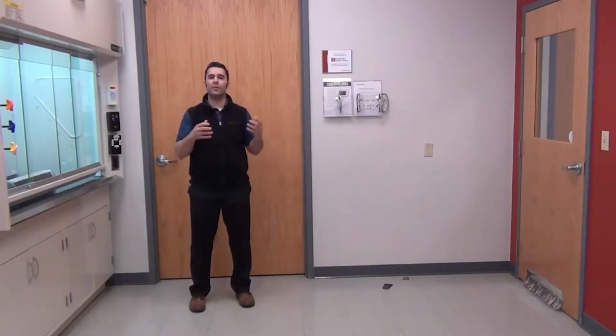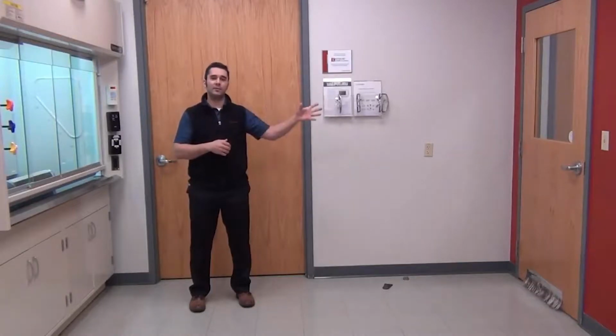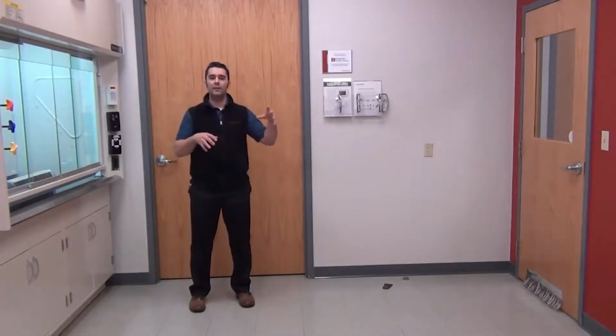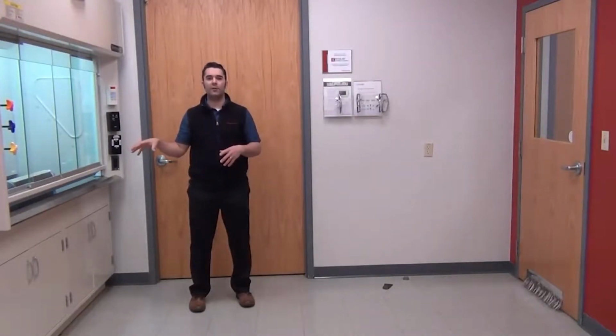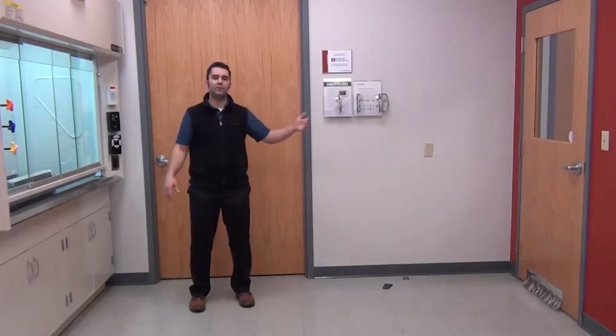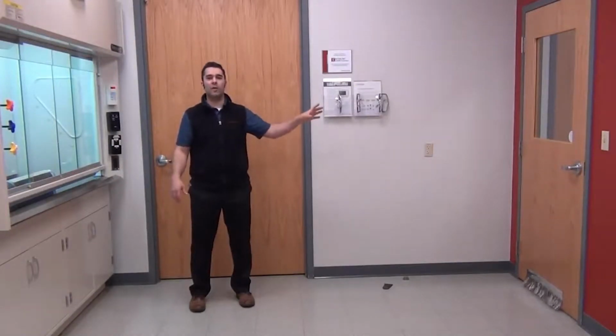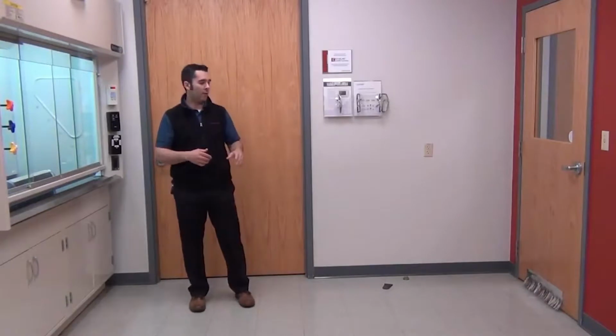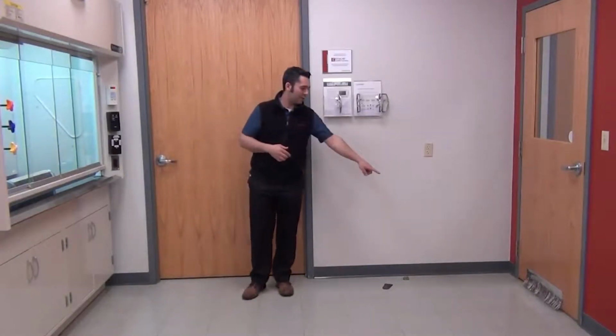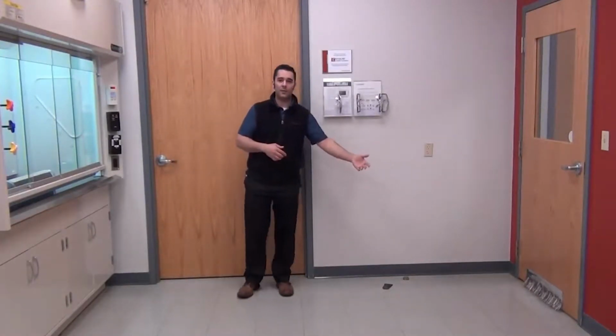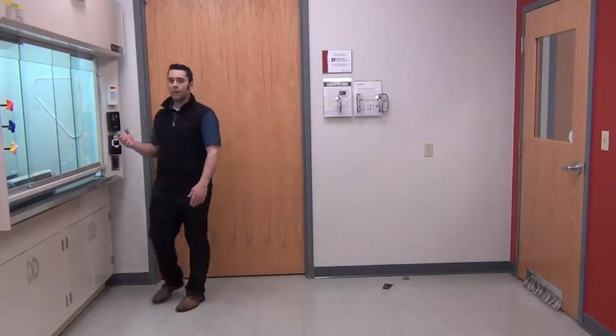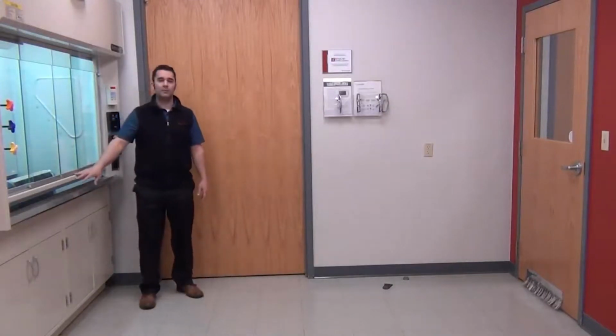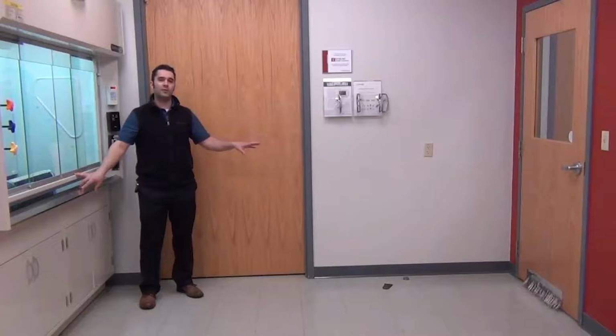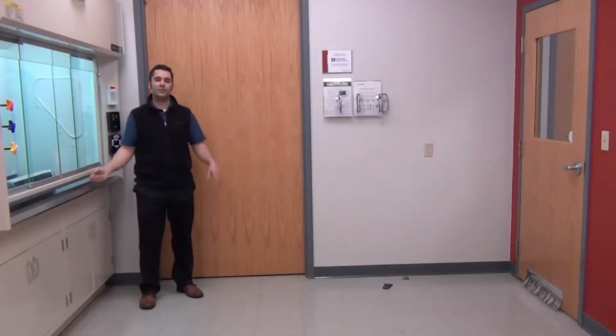So when you're looking at the pressure relationship with an adjacent space to a wet chemistry lab, the speed of response of these devices for the general exhaust and supply has to be the same as the fume hood. Otherwise, that pressure across the door is going to fluctuate, which could cause issues across the hallway. Now, if you keep your attention down here at the hula skirt on the bottom of the door, I'll demonstrate how that works. So right now I have my Phoenix Controls fume hood with a Phoenix Controls general exhaust and supply running inside of this space.